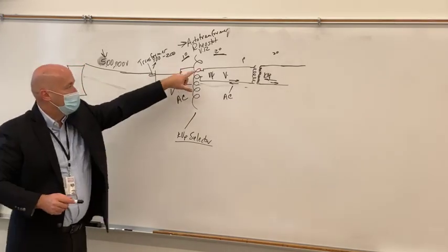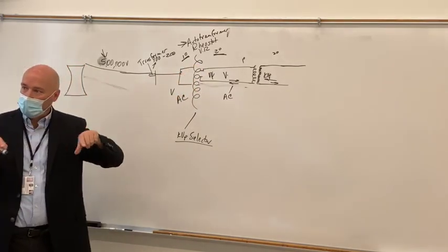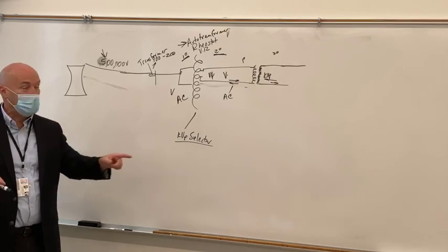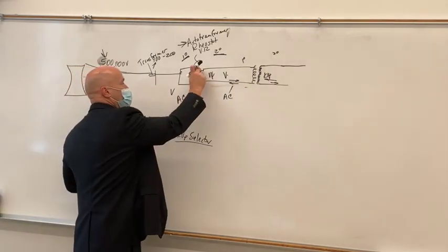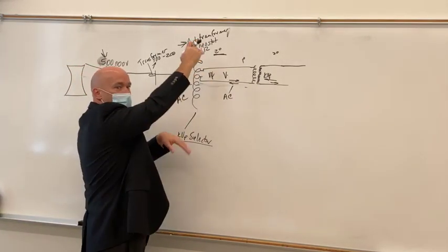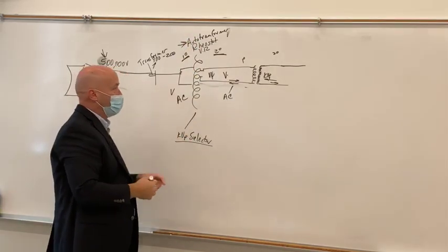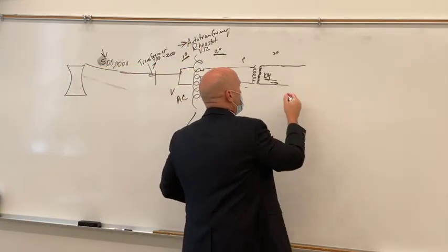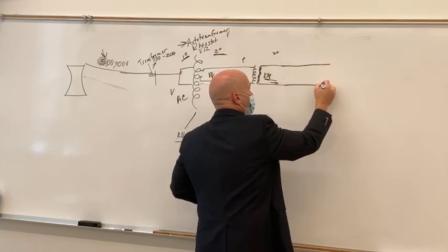That's where you're actually selecting your kVp. When you make those contacts on the secondary side, whenever you push the buttons to increase or decrease your kVp, that's what you're actually doing: you're taking these things and spreading them out, or mashing them together, okay? So it sets your kVp. It becomes kVp here. We come out of there, and what are we going into?